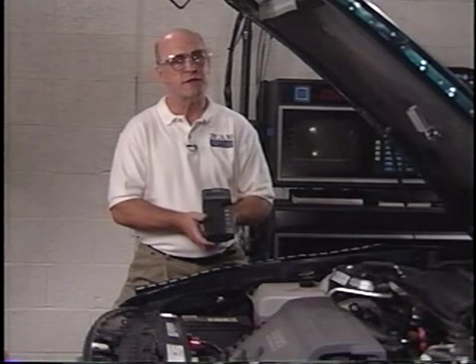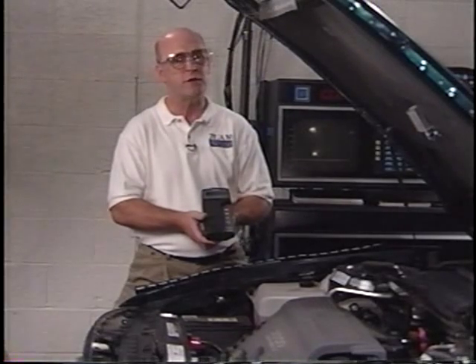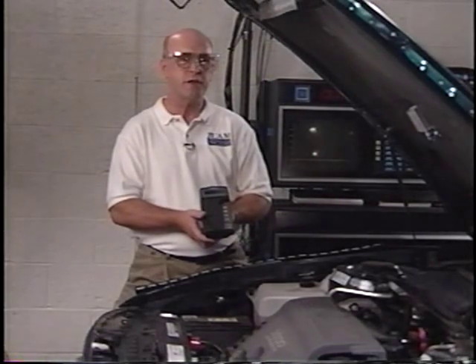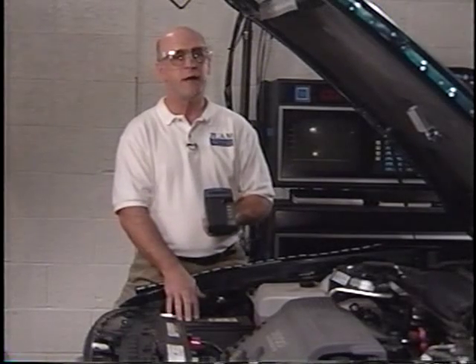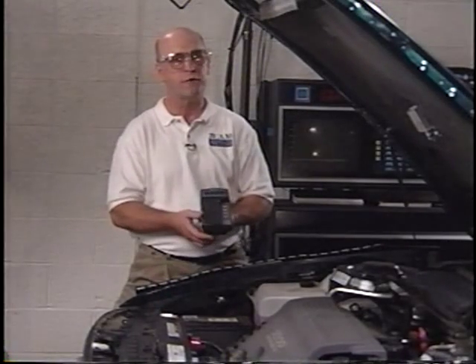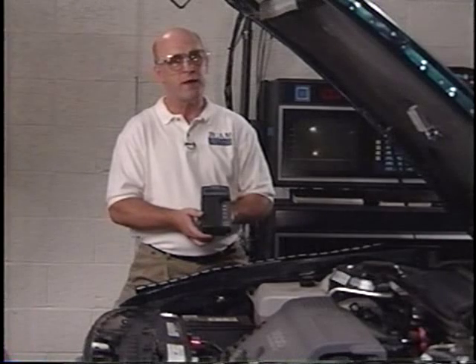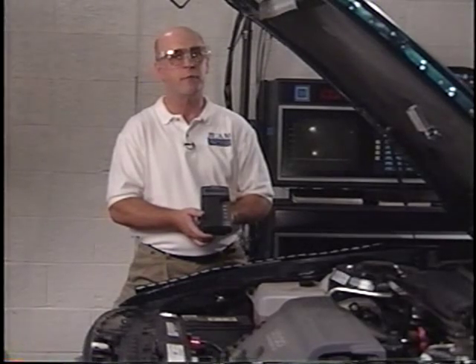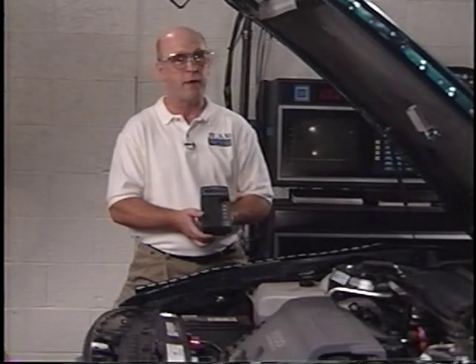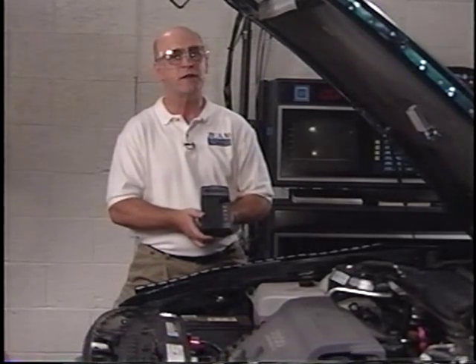The J42000 uses what's called a conductance test. What this unit does is take a small amount of DC energy from the battery under test, convert it into an AC voltage, reapply that to the battery, and measure the current that flows in response. From that calculation, we're able to give you a determination about how healthy the battery is in relation to the rated CCA that you dialed into the tester prior to test. The conductance test can be used to detect defective cells, opens, or shorts, which will limit the battery from producing the desired current.